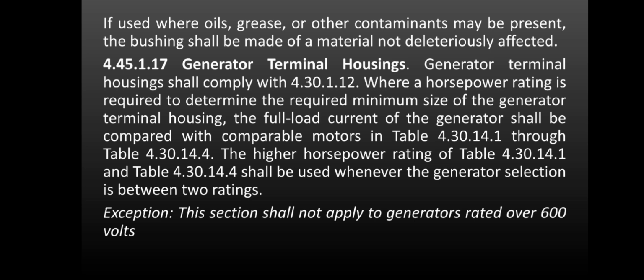General. Terminal housing. Generator terminal housings shall comply with 4.30.1.12 where a horsepower rating is required to determine the required minimum size of the generator terminal housing. The full load current of the generator shall be compared with comparable motors in Table 4.30.14.1 through Table 4.30.14.4. The higher horsepower rating of Table 4.30.14.1 and Table 4.30.14.4 shall be used whenever the generator selection is between two ratings. Exception. This section shall not apply to generators rated over 600 volts.